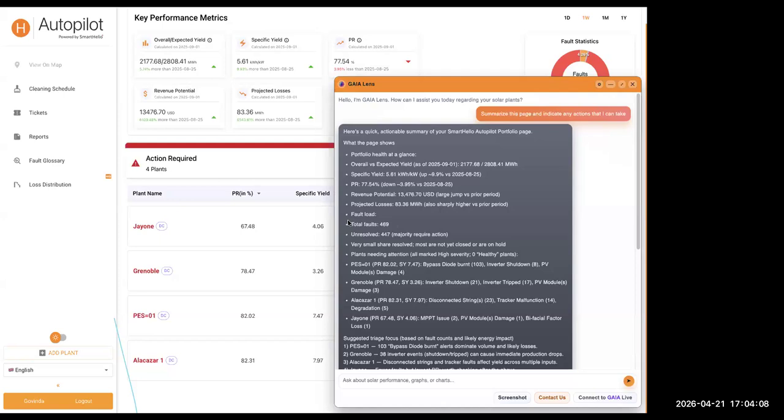generally I try to sort out what's going on with the curtailment. I try to put pictures with strings on an inverter during curtailment, because we see that the strings are not behaving the same under curtailment, and usually we have some errors also, some alarms that have to do with string feedback power.